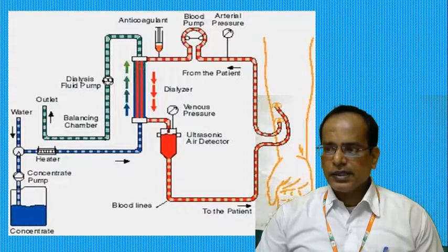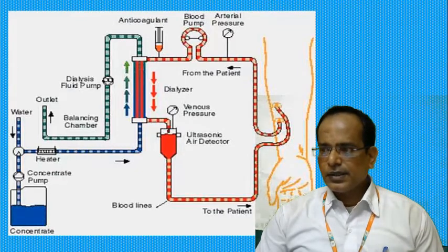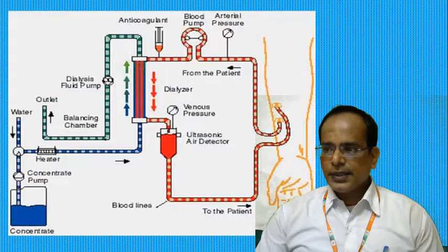These are the controls that are either part of, or peripherally related to, the kidney machines. Here a pressure alarm is provided, which is used to warn of any break in a blood tube or line from the patient.